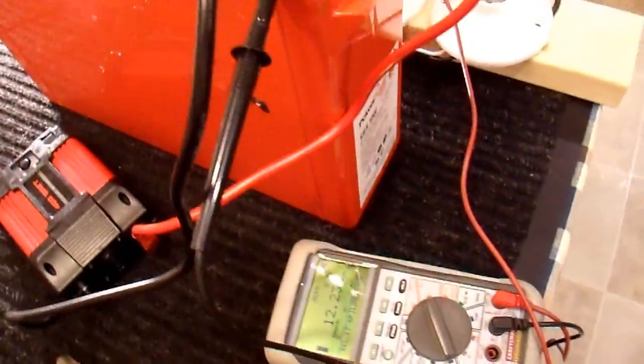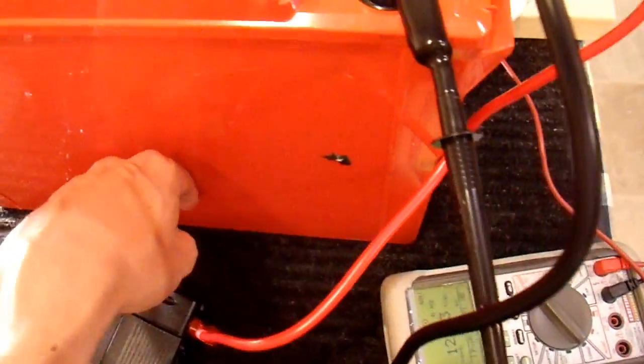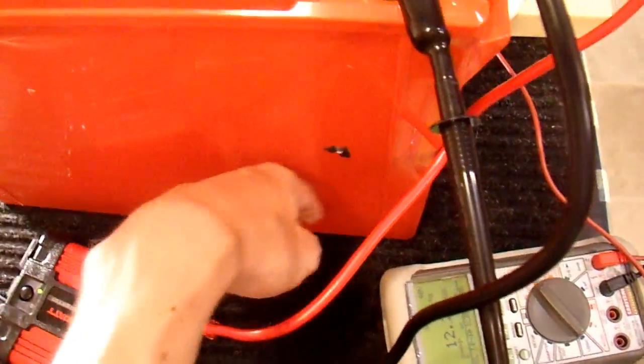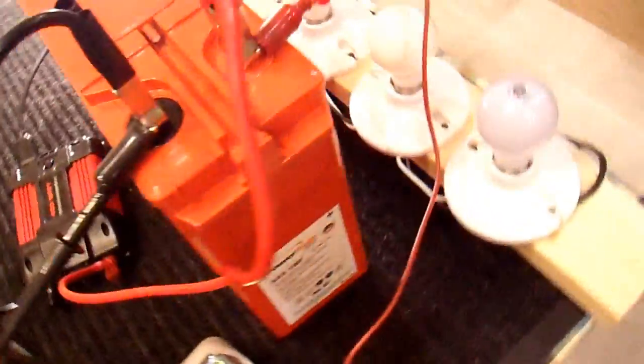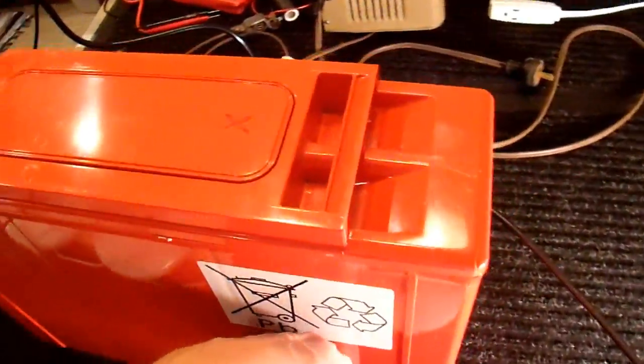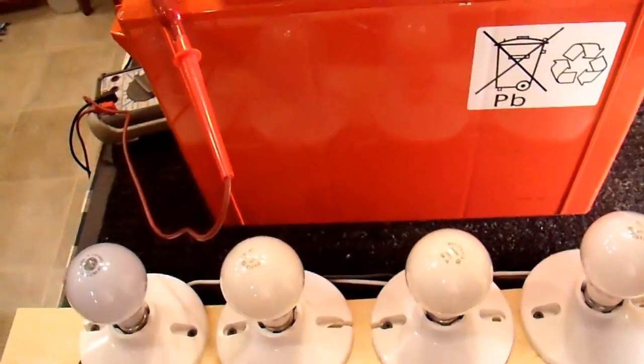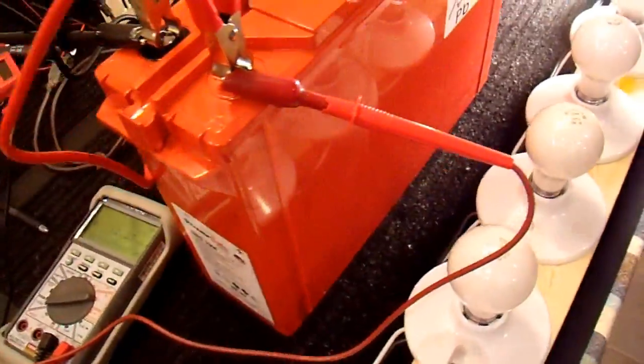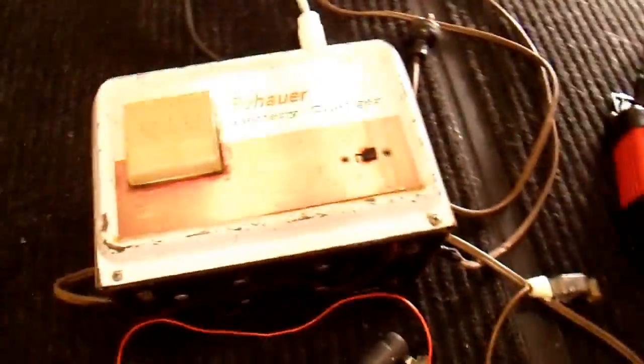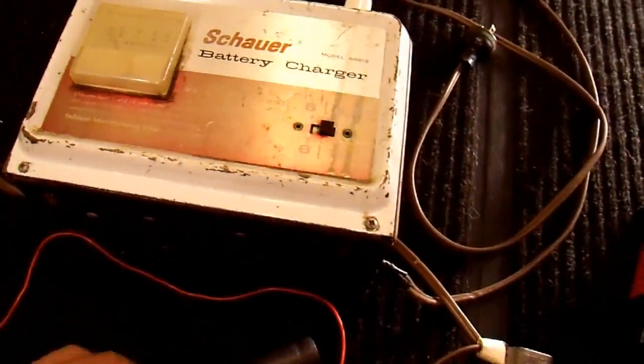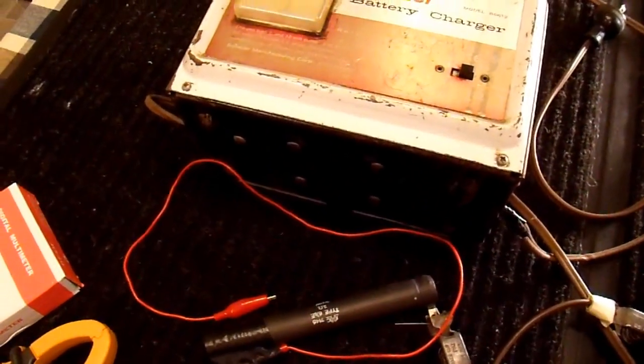Now particularly on the first cycle I want to keep track of the battery temperature and note if any of these cells get warmer than others because if they do that means that the internal resistance of those particular cells is higher than the rest and that's not good. That means that I have more work to do. That I need to put that equalizing or reformation charge on the battery for a longer period of time.